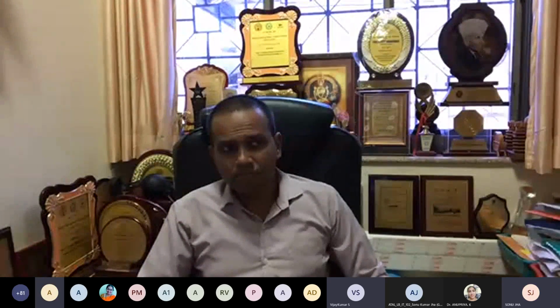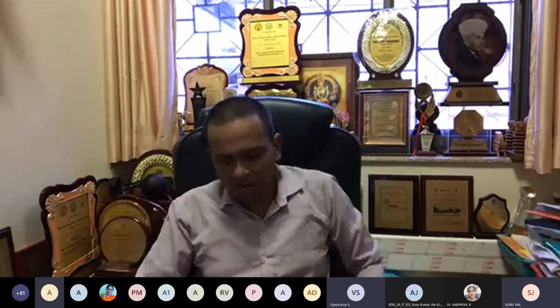Okay, so sir, those two wires, ground and reference, from where will we give connectivity for those two wires? See, normally ground is like the electricity ground connection, one ground connection to see the quality of the signal. Reference is like, for example, I'm taking from the frontal lobe, you can give a reference of that particular lobe. This reference is like a similar channel. Anyone close to the channel which you are taking, the same lobe you can give, just as a reference. Ground is like a ground connection to check the quality, rather than seeing the accuracy from the actual electrode wires. You can take one extra ground connection. It is like a ground connection in your electrical circuit.